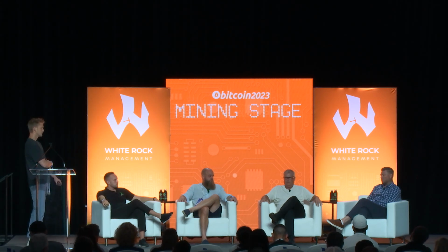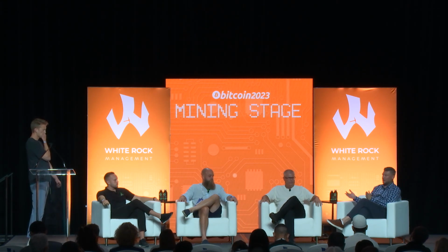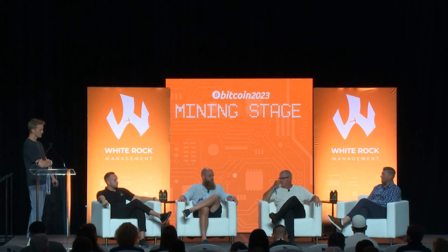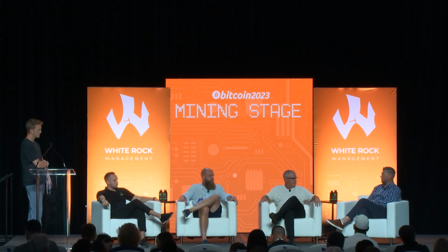And by doing that, if you're changing filters less often by using a higher efficiency, longer lasting filter, you're also throwing away filters less often. You're also shipping filters less often. You're also receiving filters less often. So really, with that total cost approach, if you can not touch it and it performs and it protects your data center, the longer you can do that and still maximize your airflow and dissipate your heat in your operation, the better off you're going to be.